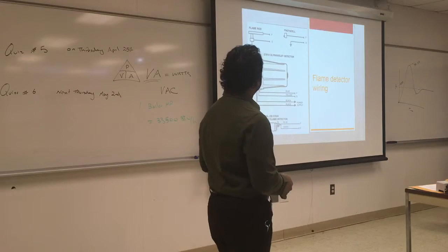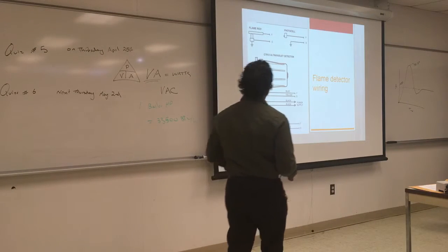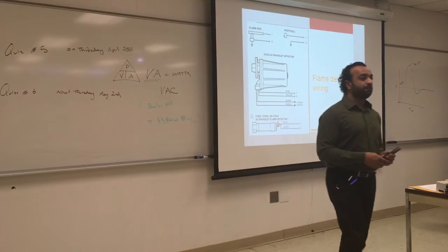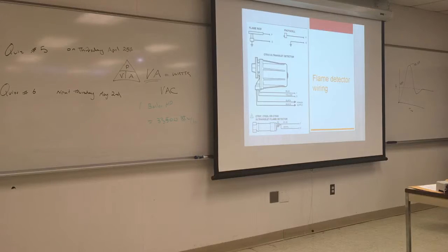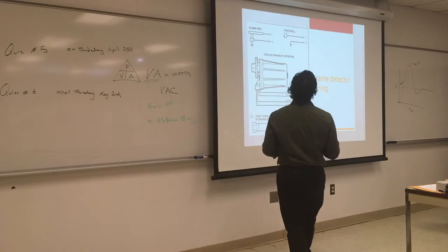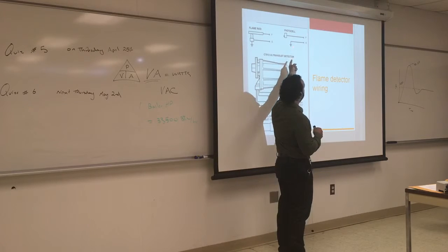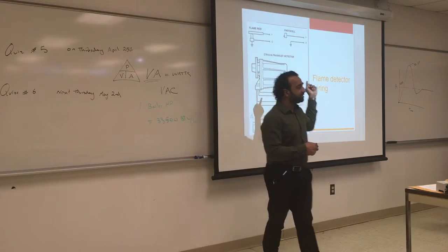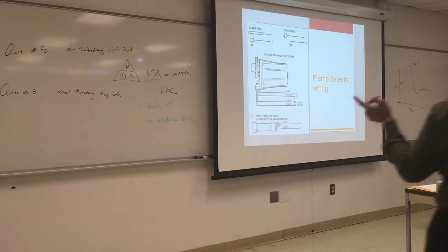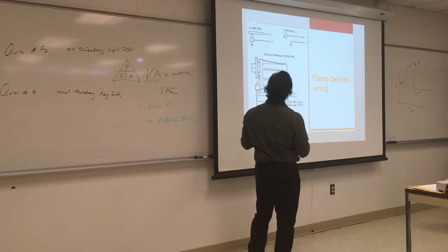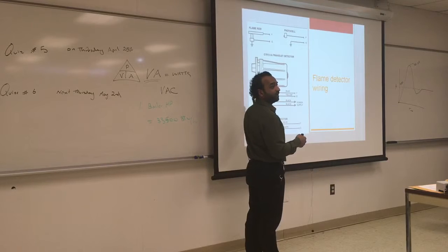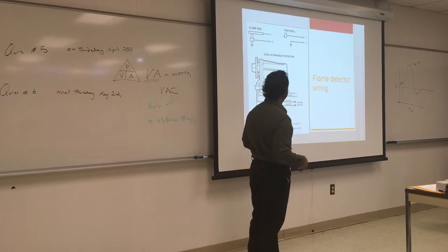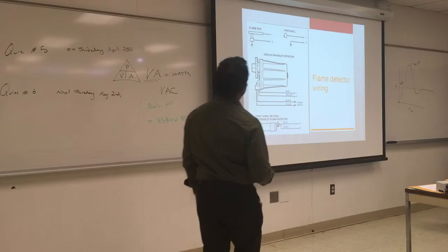These are some of the flame detectors, flame rod or photocells. So remember the terminal for the cad cell, what was it called in residential? FF. Now we have FG. Why? Because F is for flame, to detect flame, and G is the ground. So you always need a ground for this controller, because we're changing AC to DC, and we are using our rectification system. So we send the flame to a ground, and the AC current going into the flame will come back as DC.